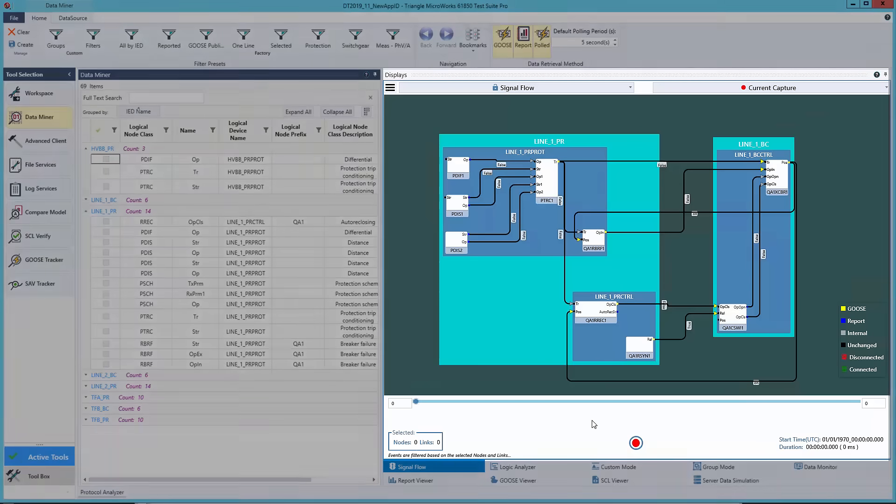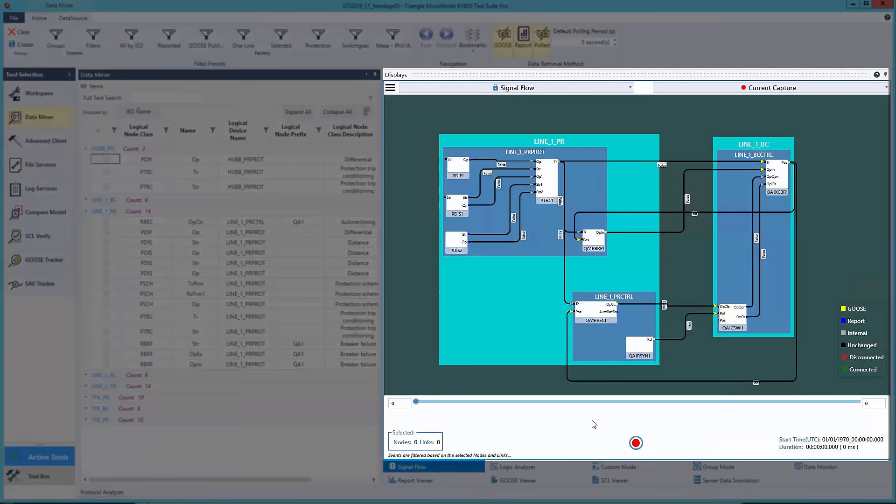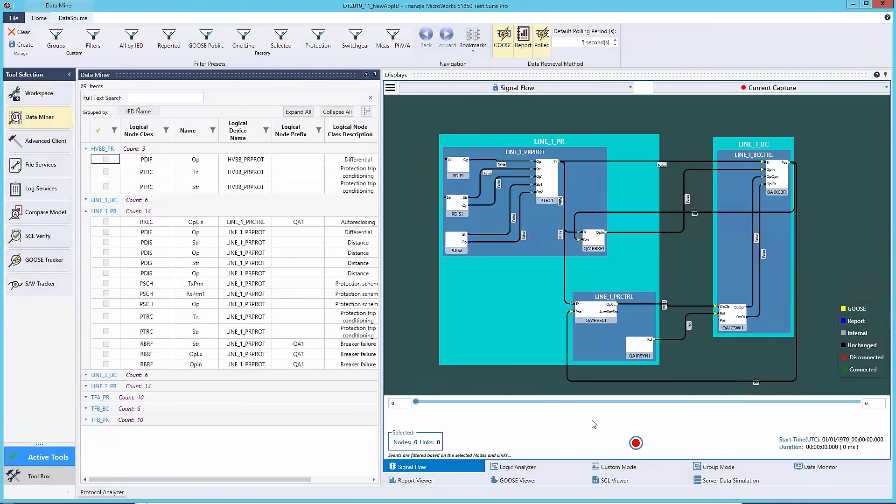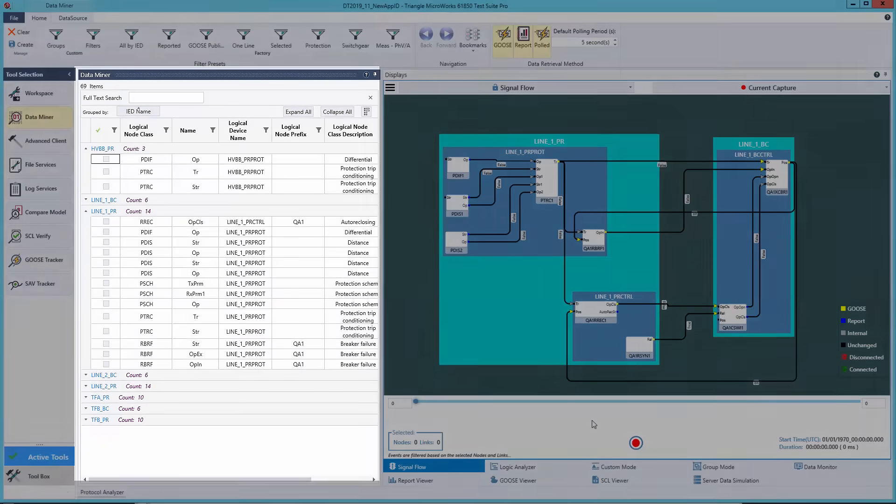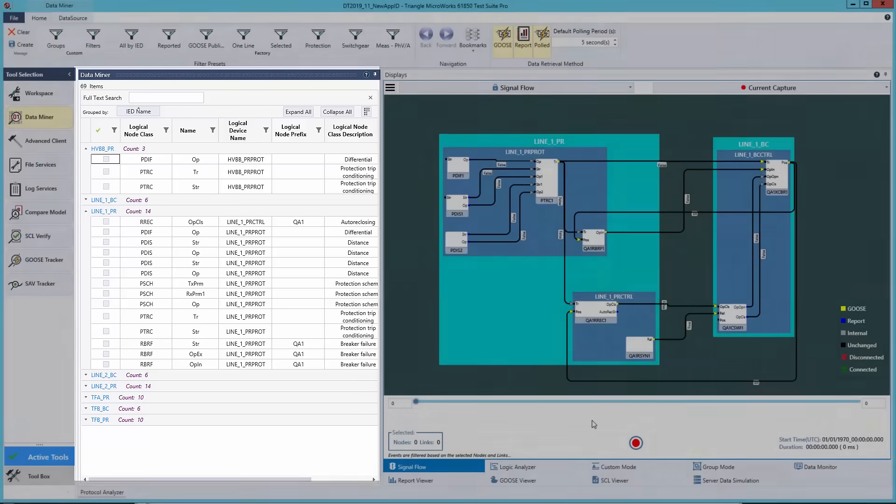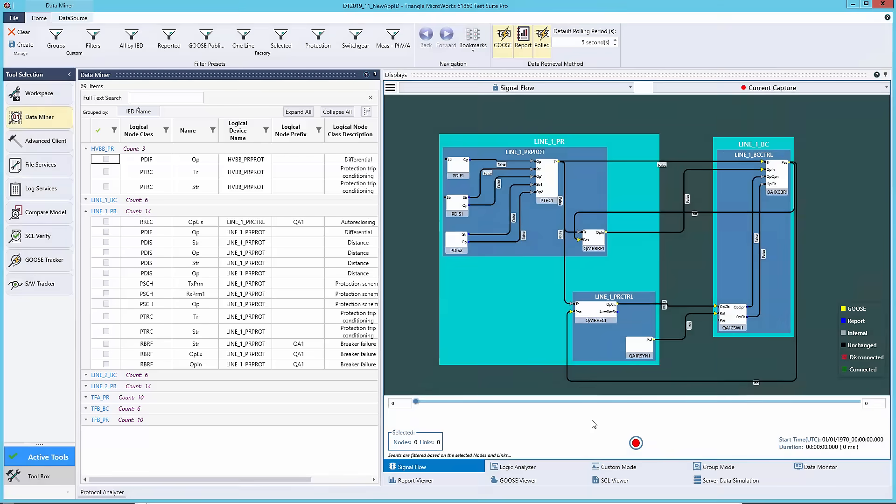This is our signal flow diagram. You can create this type of diagram by dragging logical nodes from the data miner to this display. When a logical node is dropped on the display, it will pull all other logical nodes it needs to communicate with via Goose automatically. Reporting and internal connections can be added as well.